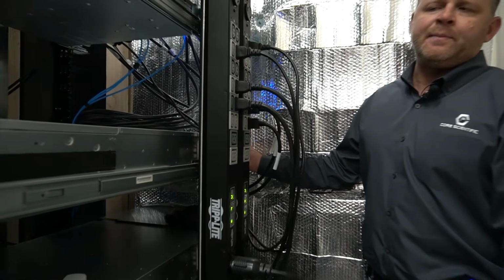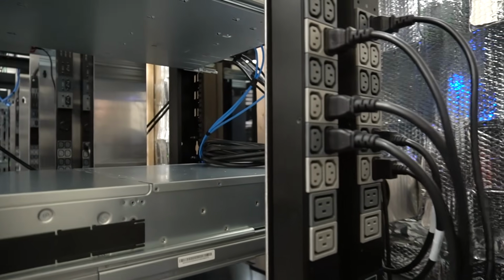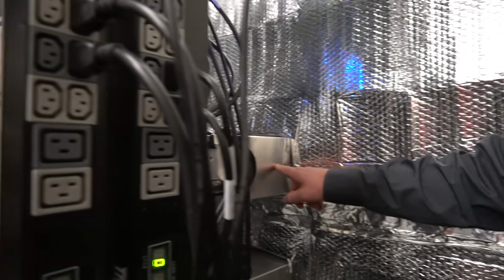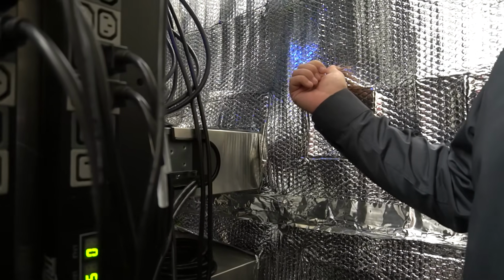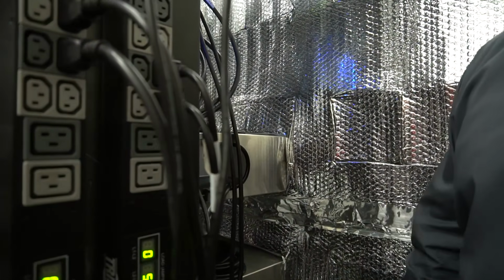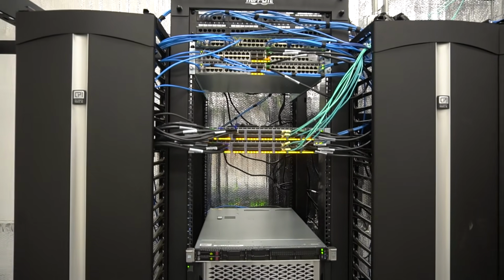In a typical data center, you blow the air conditioning through a raised floor up through the racks. We've built custom shrouds and exhaust the heat into our hot aisle, so we don't have to keep as much air conditioning inside the space.